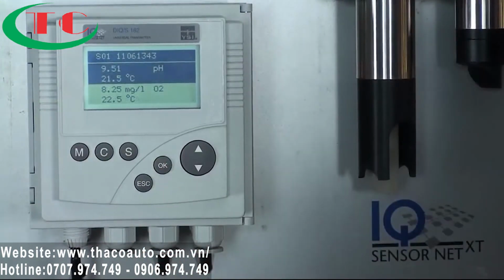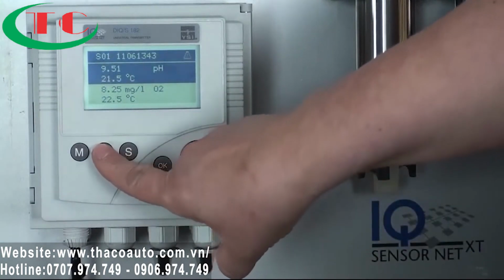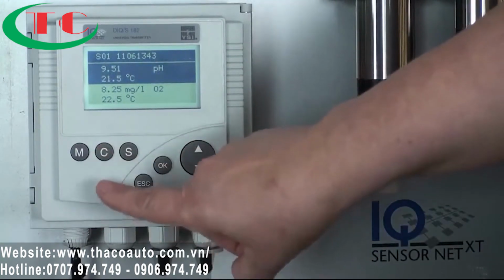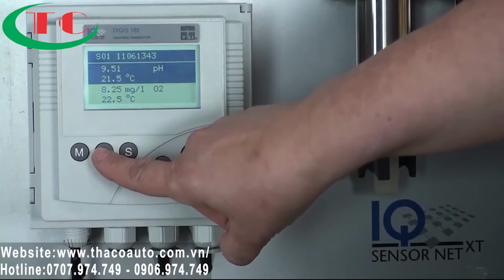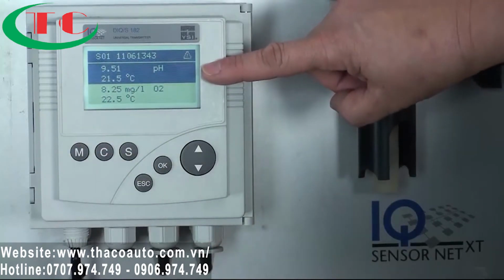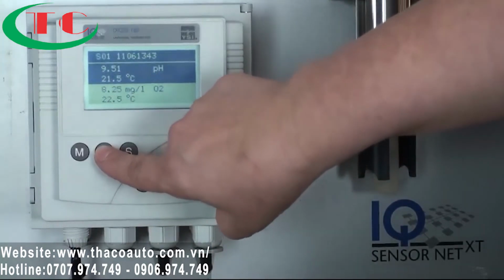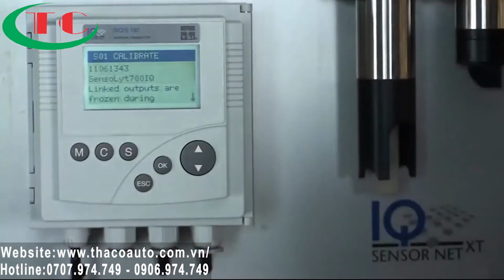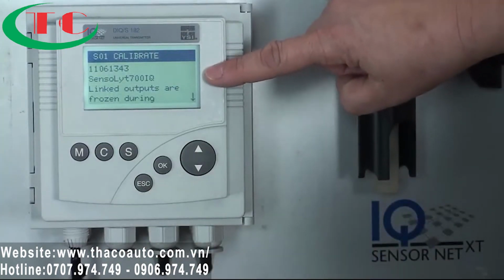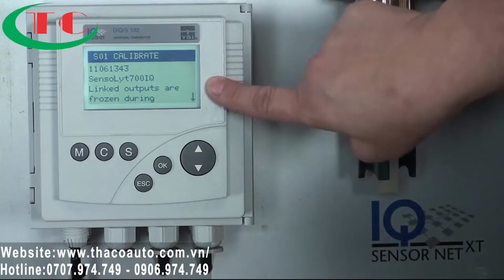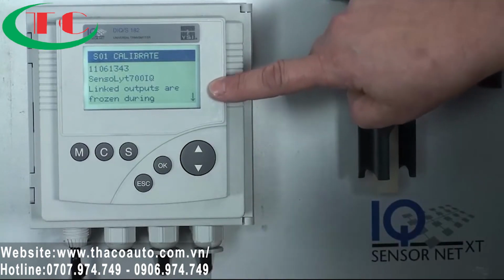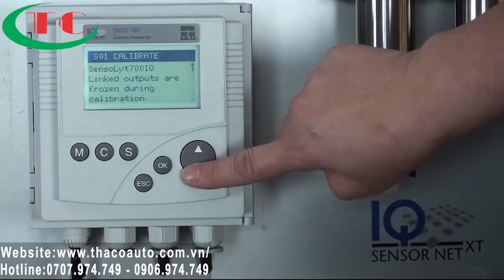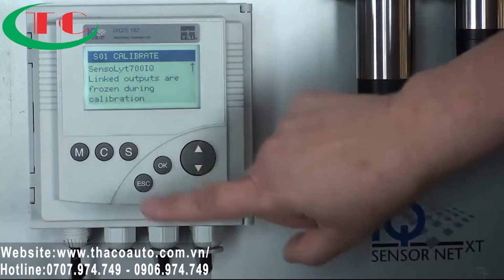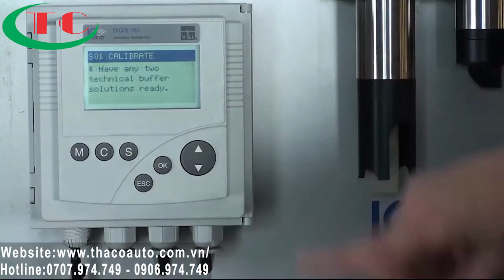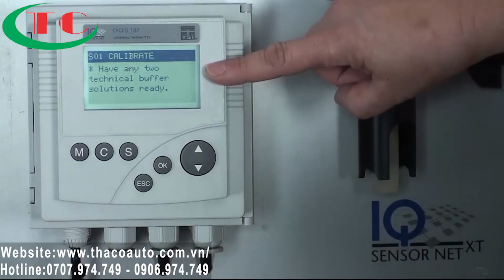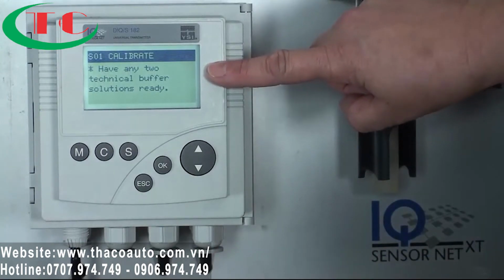So let's go back to the main screen. I told you about the C button for calibration or for a sensor check. I've got my pH sensor highlighted. So if I hit the C button with the pH sensor highlighted, that is going to go into the SensorNet. And it says the linked outputs are frozen during calibration. So at this point I could say OK. That freezes it, and then it's going to walk me through a calibration.